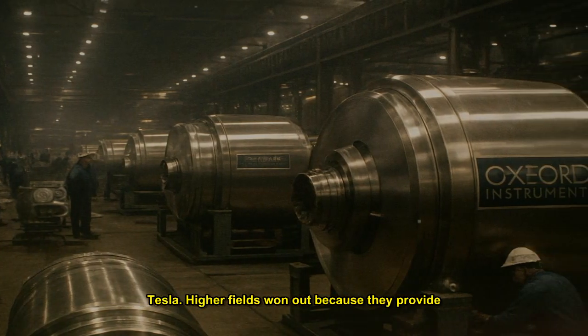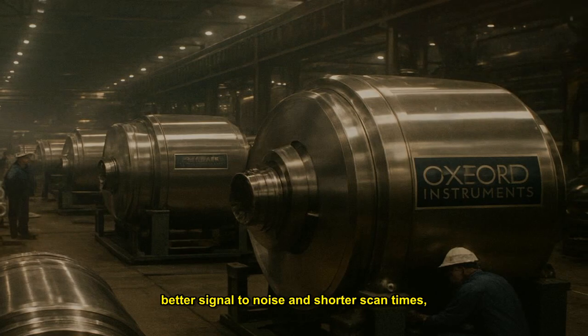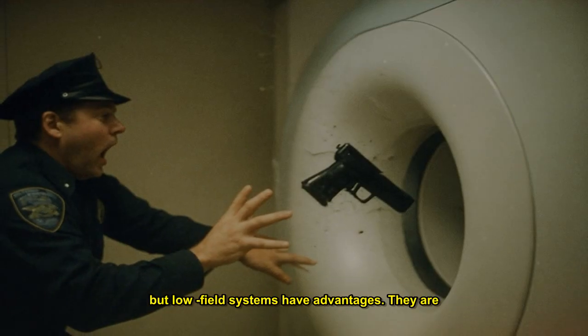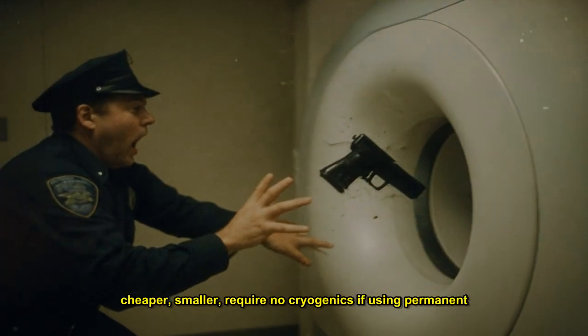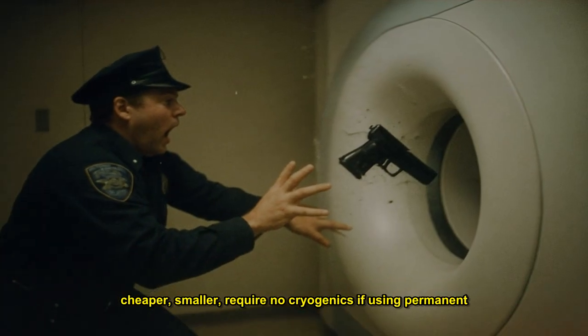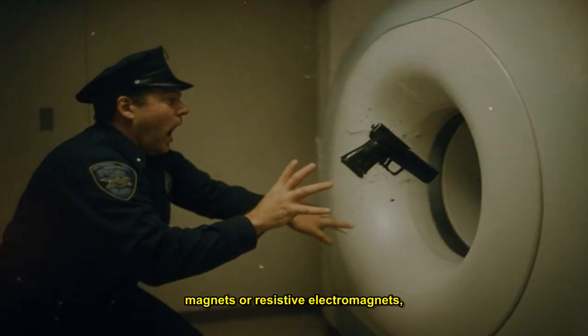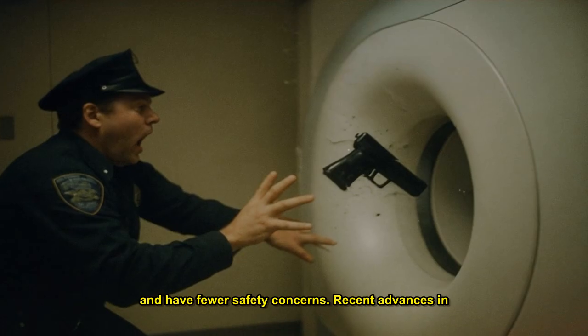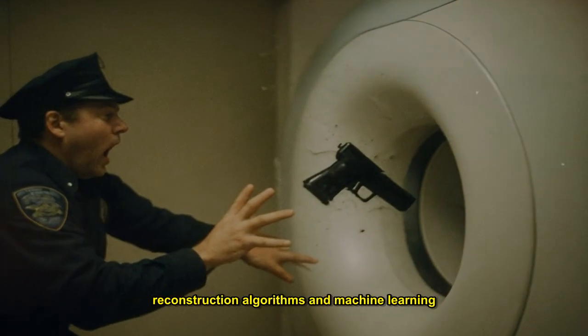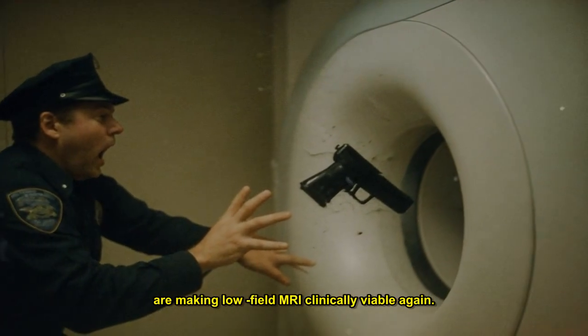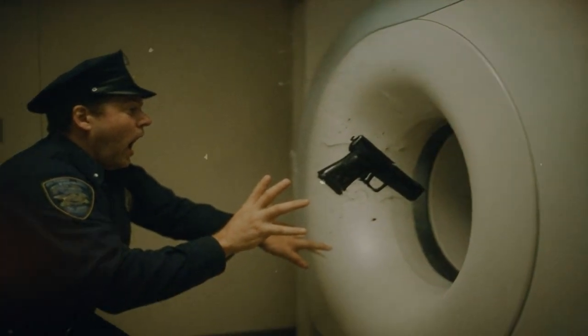Higher fields won out because they provide better signal-to-noise and shorter scan times. But low-field systems have advantages. They are cheaper, smaller, require no cryogenics if using permanent magnets or resistive electromagnets, and have fewer safety concerns. Recent advances in reconstruction algorithms and machine learning are making low-field MRI clinically viable again.